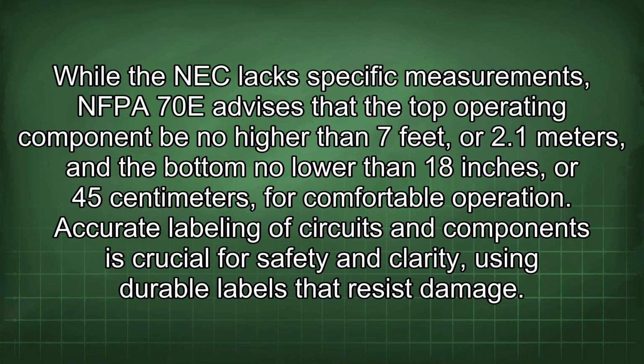While the NEC lacks specific measurements, NFPA 70E advises that the top operating component be no higher than 7 feet or 2.1 meters and the bottom no lower than 18 inches or 45 centimeters for comfortable operation. Accurate labeling of circuits and components is crucial for safety and clarity, using durable labels that resist damage.